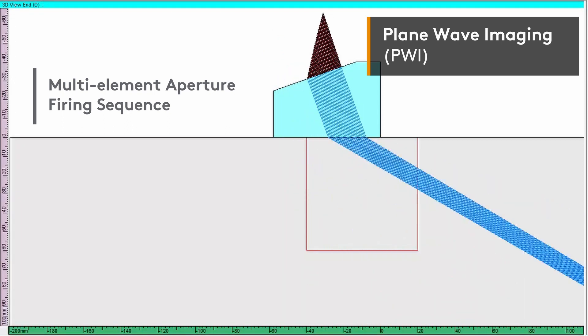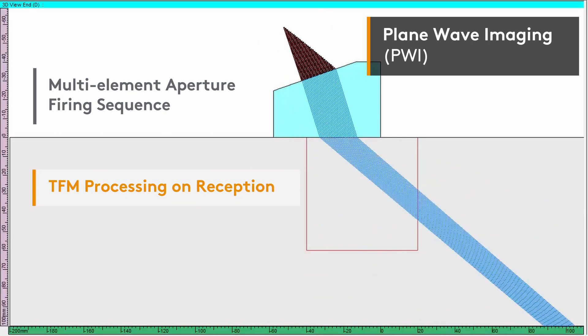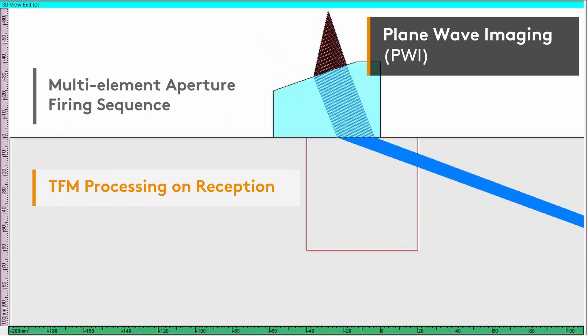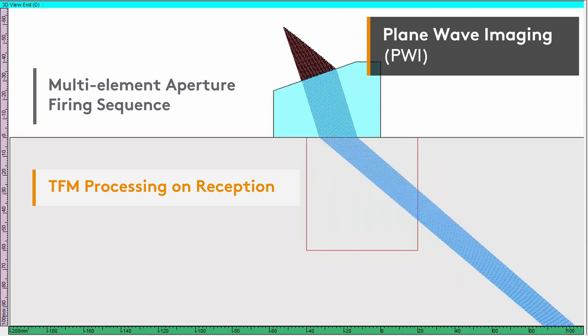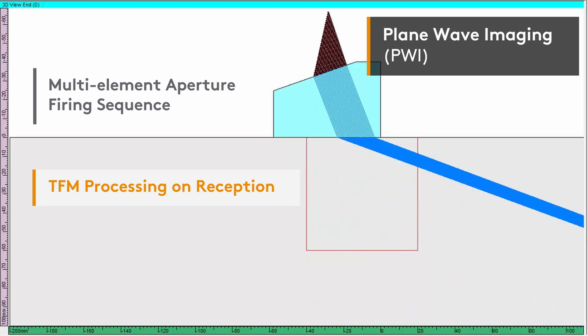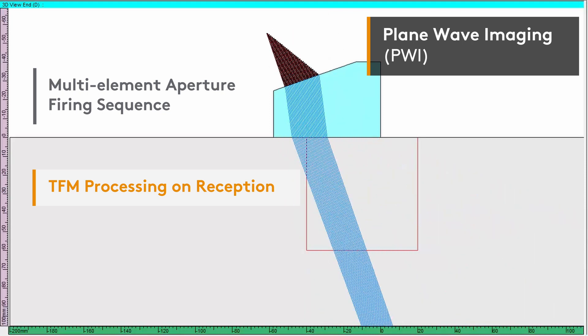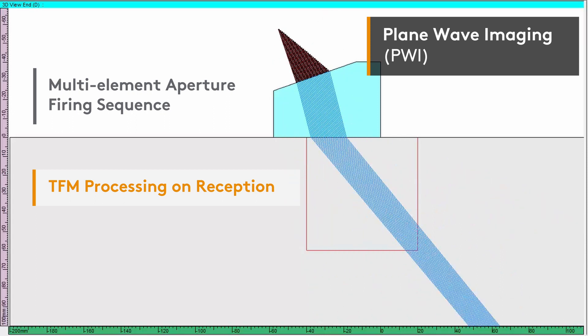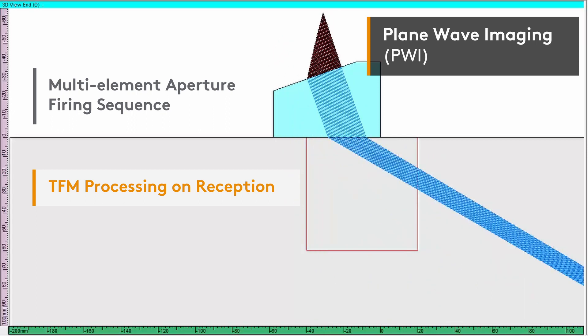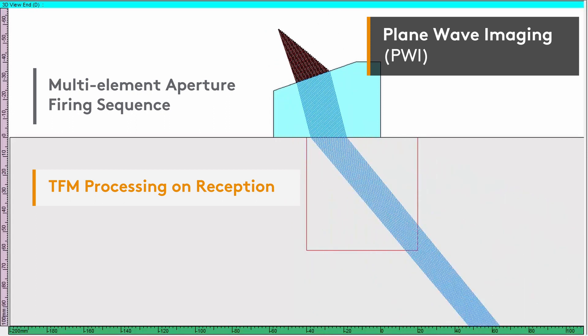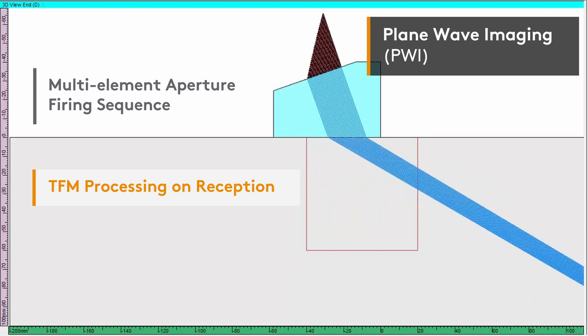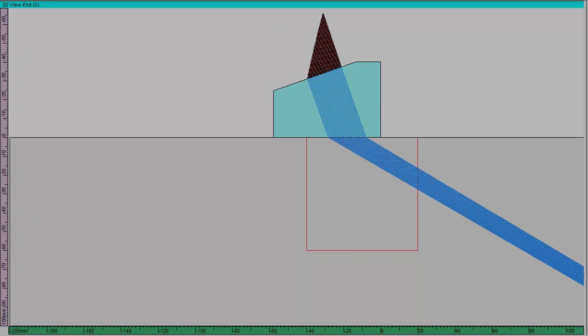The receiving process is done with each element individually and a TFM frame is processed from the raw data. Live PWI TFM imaging is done during inspection and the encoded data can be saved just like for regular phased array UT or live TFM.